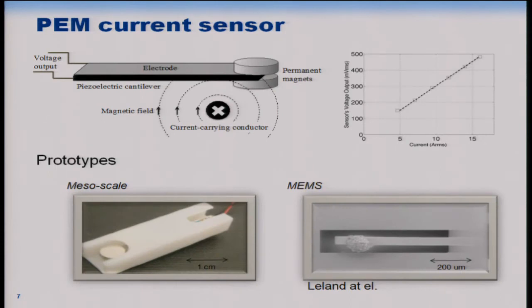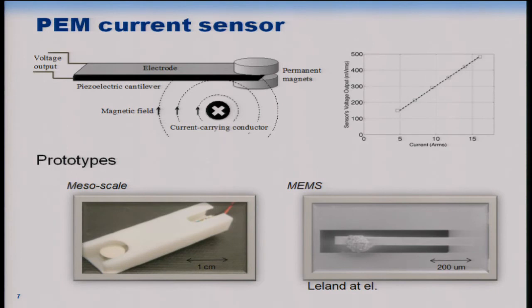You might wonder what kind of sensor can measure current outside of the breaker panels. We have been working on this for more than four and a half years. The idea is a piezoelectric cantilever with permanent magnets mounted on its tip. When placed in a magnetic field, the magnetic force deforms the cantilever, generating a voltage proportional to the current flowing in the conductors. Through modeling and testing, we confirmed the voltage output is linearly proportional to the current.